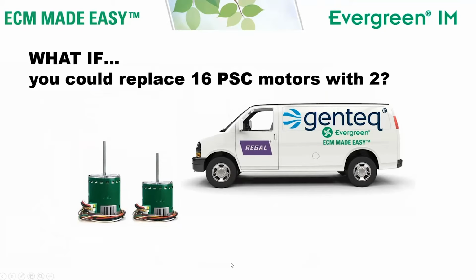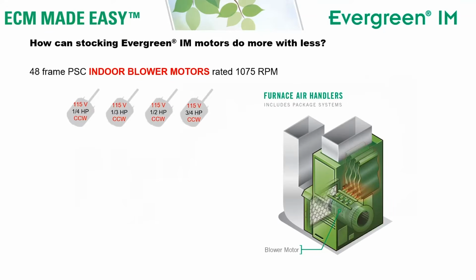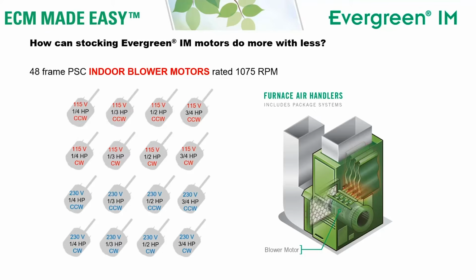What if you could replace 16 indoor PSC motor ratings with just 2 motors? The Evergreen IM motor is designed to replace 48 frame PSC indoor blower motors rated 1075 RPM in furnaces, air handlers, and package systems. To cover all of the motors in those applications, you would need 115 volt rated motors counterclockwise from 1/4 through 3/4 horsepower. And of course, you would also need those in clockwise. To cover the air handlers and the package systems, you would need all of those same ratings in 230 volt rated motors. That's 16 motors.